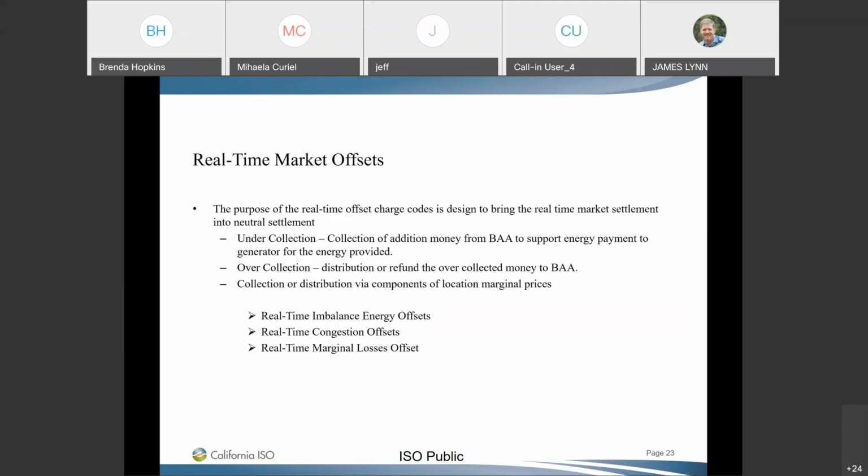We use this difference to weight how much that price should be used in calculating the real-time market hourly LAP price. And the reason why we do that is most load, when it is submitted as an hourly value, is distributed across the 12 intervals. When we're trying to weight those intervals, each of the 5-minute intervals, so that we can narrow the separation between what we pay the generator and charge the load.